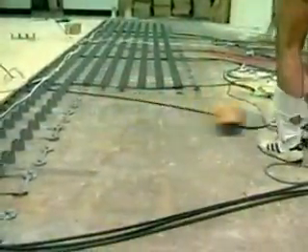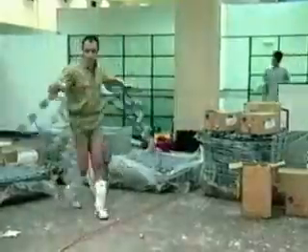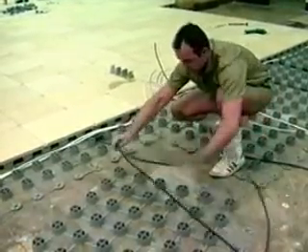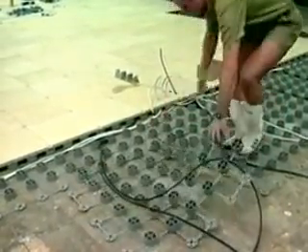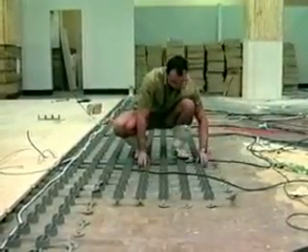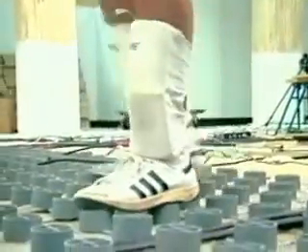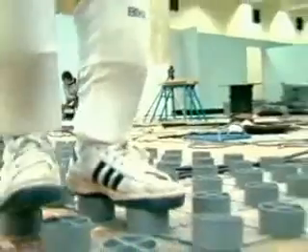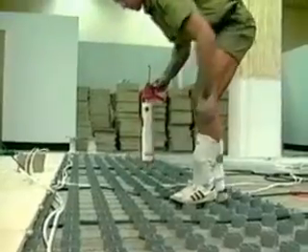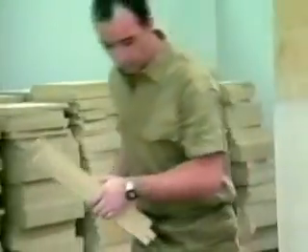Once the subfloor has been swept clean, the support modules are taken from the pallet and laid out, either parallel to the setting out lines or parallel to the previous row, as is the case here. Now, the next square of understructure is positioned onto the interconnecting pads and clicked into place. The same procedure is repeated until the row is complete. Rows are laid down one at a time, reducing the need to walk on the cylinders. The understructure is fixed to the floor with adhesive under every fourth cylinder. This gap-filling adhesive helps overcome uneven floor surfaces.